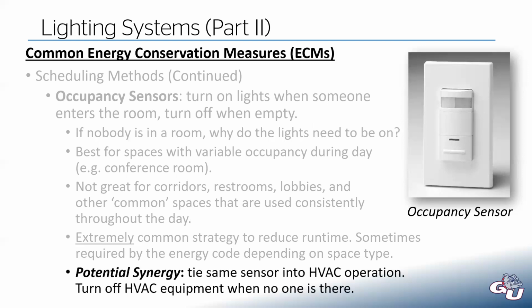A potential synergy here is we can use these occupancy sensors, which are controlling the lighting, but also piggyback off of them for the HVAC system that serves that room. Now you're able to save energy on both the lighting side and the HVAC side. And if they're already installing the occupancy sensor anyway, it's a pretty low cost to also integrate that into the HVAC.